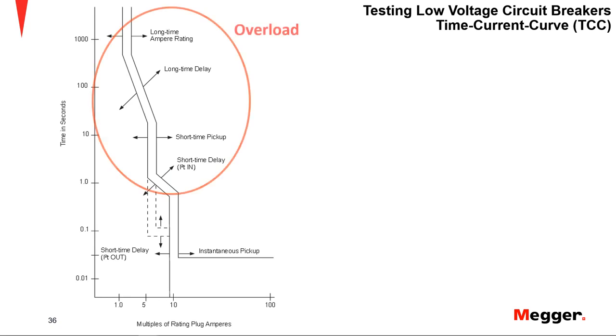And we can highlight two important sections of the curve. The first one is overload, which will tell us how the breaker will behave when there is an overload. And as you can see, I have two internal sections in this overload part. First of all, the short time. The purpose of the short time setting, or that section of the performance of the breaker, is to allow a time-based delay to elapse before tripping the circuit breaker for moderate current faults. Examples of these types of overcurrents would be the inrush on a large motor starting, or a transformer inrush when it's first energized.